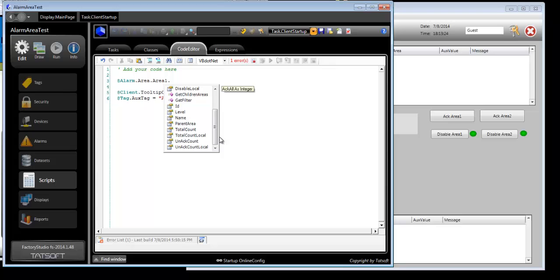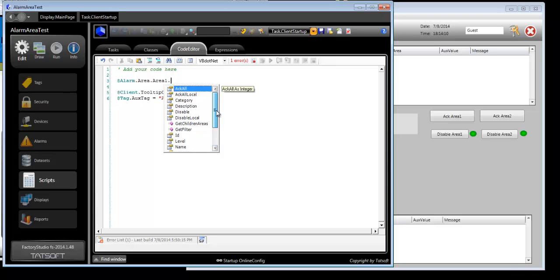Total count unacknowledged is the total number of unacknowledged alarms of that current area, including child area. Total count Local excludes the child areas. Unack count Local is without the children areas. Plus you'll see that there are ways to acknowledge all for the entire area or just for the entire area without the child area.